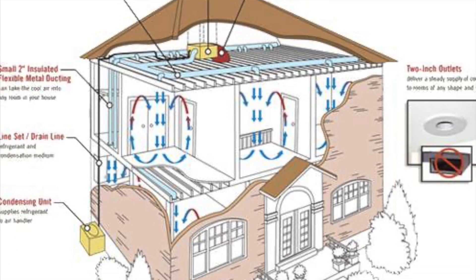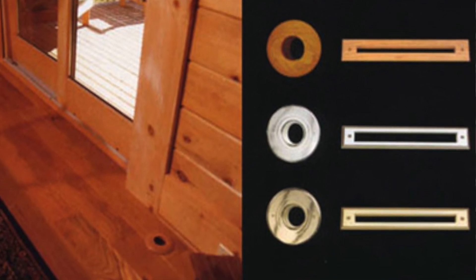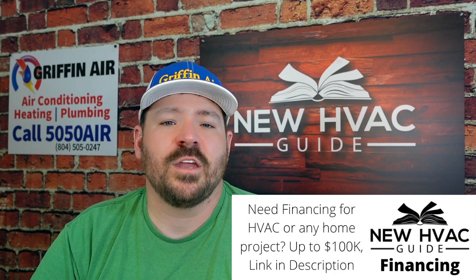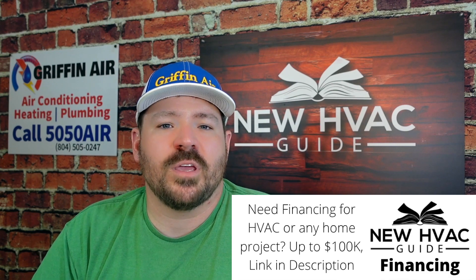Another option might be small duct high-velocity units. The brand we've installed the most of is Unico — a small duct high-velocity brand where you can pair it with an outdoor unit. The ducts are pretty small, like two inches. Instead of a six or eight-inch duct running to a space with a normal boot, you've got these small holes. They cater to historic buildings where there's not really room to run ductwork without taking away from the beauty of the building.